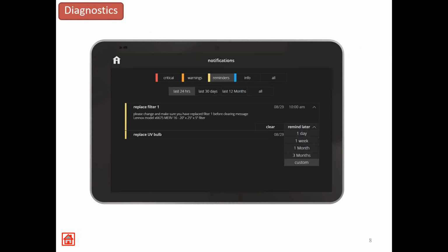All right, so let's dive into the diagnostic side of things. When you go into the notifications, you're going to have multiple options. Across the top here, you'll have red as a critical alert, which means it's something very serious. And more than likely, it's going to shut the unit down where it won't operate and function. How quick we shut it down is based on how many alarms it may have hit, the intensity of the alarm, and what damage could be caused from it.